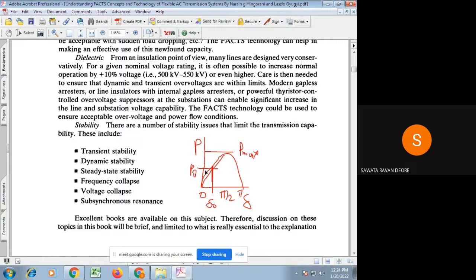But if a very large disturbance has to be sustained, then you need to keep a large stability margin, and for that reason the operating angle delta is kept in the range of 30 to 40 degrees only, so that if any large transient takes place, the machines will still be able to maintain synchronism with each other. So that is governed by transient stability. Another term is dynamic stability.